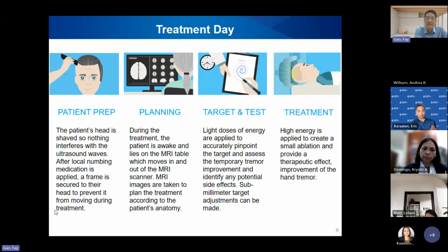During the procedure, the patient is positioned in the MRI scanner with a water bath that's allowing the ultrasound waves to go through, but it still allows MRI scans to be obtained. And then we do usually 3 test sonications. So these are low-level ultrasound that just causes a slight elevation in temperature. These are done for calibration to confirm that the temporary thermal lesion is the size, shape, position that we want.